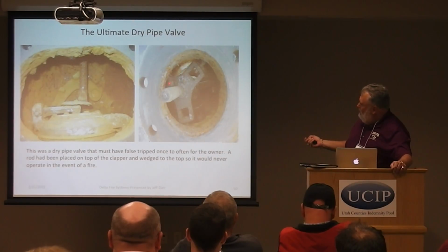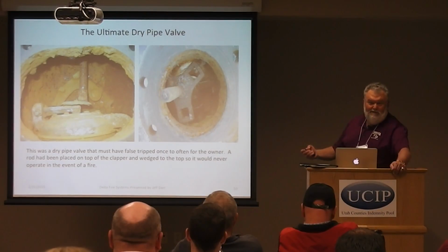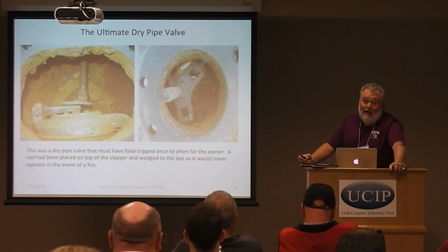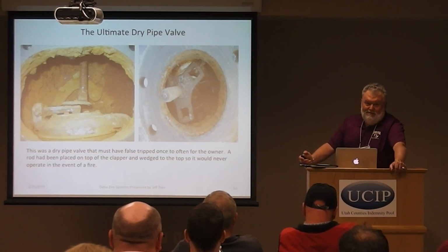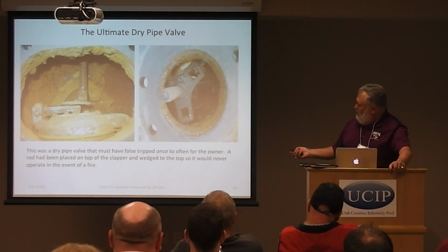Here's that rod coming up. He devised this little device with set screws that would, if that valve tried to trip, push it up tight against the top here and never allow that valve to operate. So I don't know how many years that system had been in service with the control valve wide open, everyone thinking that they had a system that was in operation, but it would have never operated. So just a word of caution there.